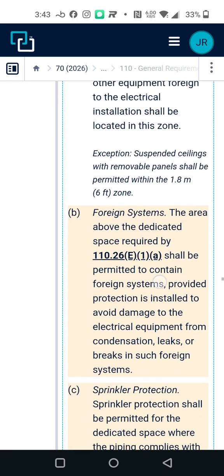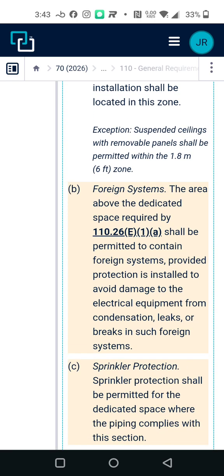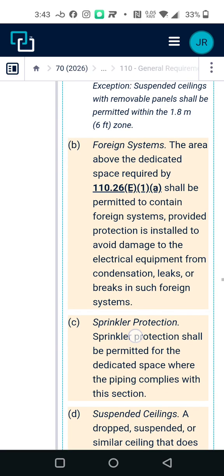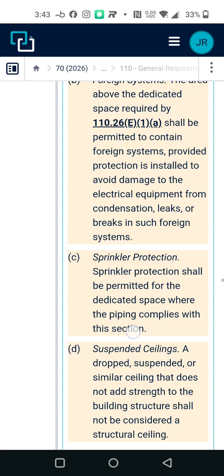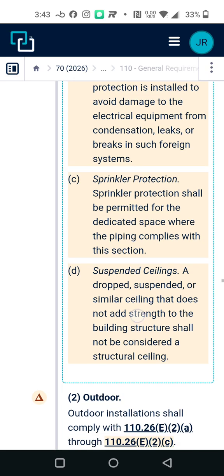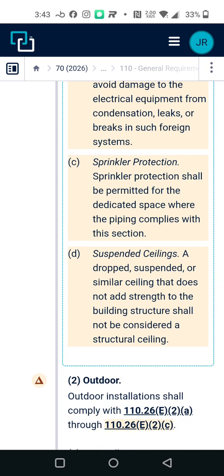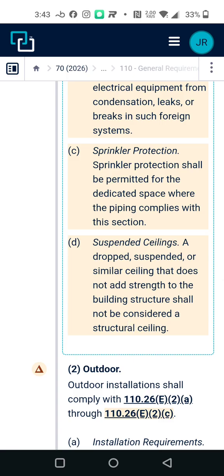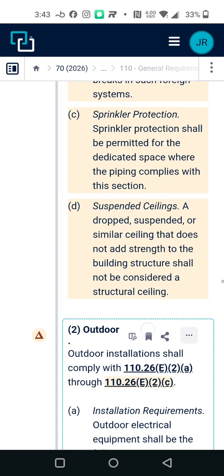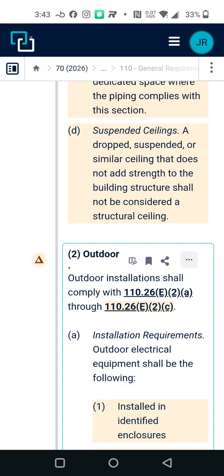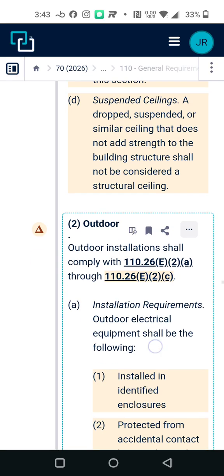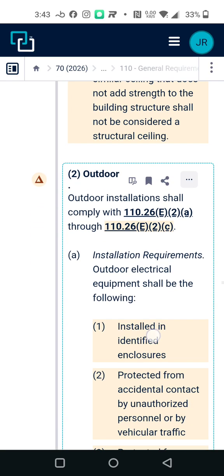Foreign systems: the area above the dedicated space required by 110.26(E)(1)(a) should be permitted to contain foreign systems, provided protection is installed to avoid damage to the electrical equipment from condensation, leaks, or breaks in such foreign systems. Sprinkler protection should be permitted for the dedicated space where the piping complies with this section. Suspended ceilings: a drop, suspended, or similar ceiling that does not add strength to the building structure should not be considered a structural ceiling. Outdoor installation should comply with 110.26(E)(2)(a) through 110.26(E)(2)(c).